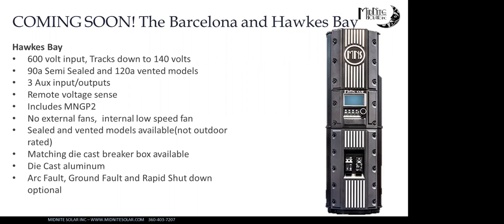So in the Hawke's Bay and Barcelona we've built in a self-powered circuit that monitors the battery voltage. If the battery terminal voltage goes above a safe level, it remote trips the breaker in the breaker box for those two devices. It's an extra safeguard, because not every BMS will safely open if the voltage spikes quickly—they can arc over and bad things can happen. That's a feature we were requested to add, so we did.